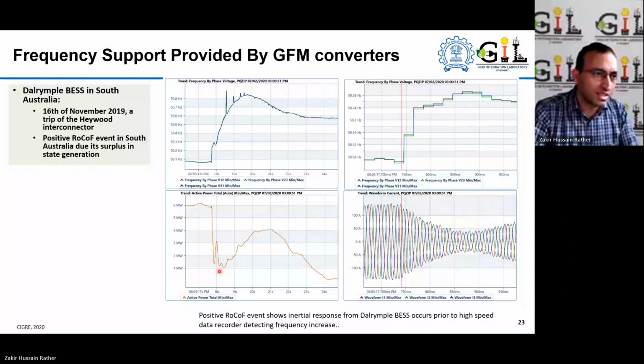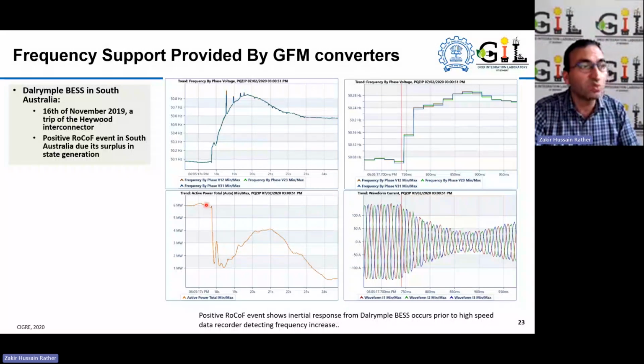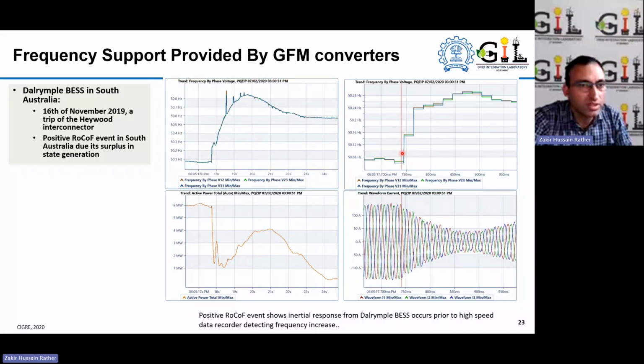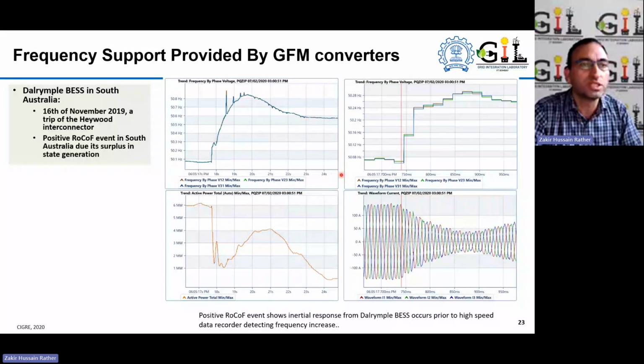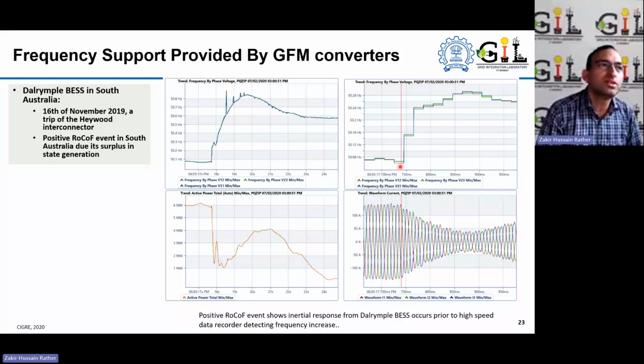It is actually changing its power. It was 6 megawatt. Now it is decreasing this power in response to the increase in frequency. So what is shown on these right side plots is that the frequency change starts somewhere here. This is the zoomed version of the frequency change here. But if you see, the current from this IBR interfaced BESS starts decreasing earlier than the frequency change. Which indicates that it is providing the inertial response even before the change of the frequency of the grid.